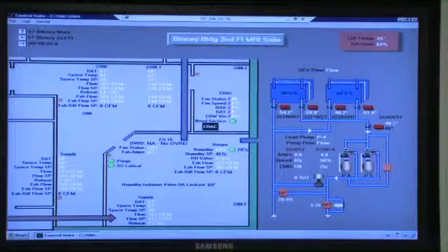Okay, I'm going to move on to the water side. Now, each MRI, as you know, has a shield cooling system. So we have to provide the shield cooling, and I'm assuming it's in here. Help me out, Steve, if you know. All this water that's supplied here goes into this room. Actually, that shield cooling system supports the other MRI as well.